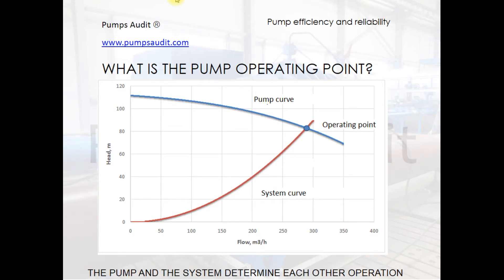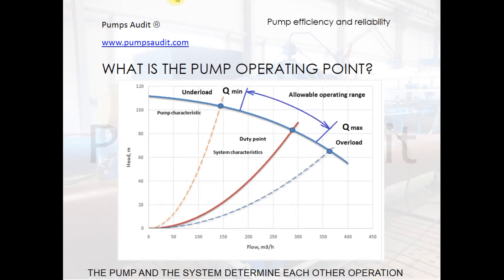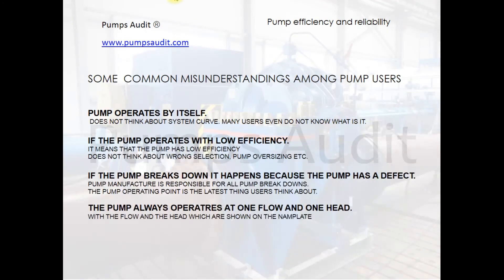The pump works in the system, not by itself — this is the main idea to keep in mind, but pump users very often forget it. The pump operating point moves along the pump curve depending on how the system characteristic changes over time. It can lie within the allowable operating range, giving high efficiency and reliability, or go outside it, resulting in low efficiency and low reliability.